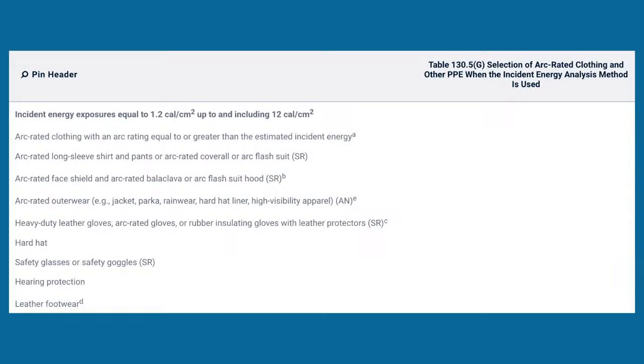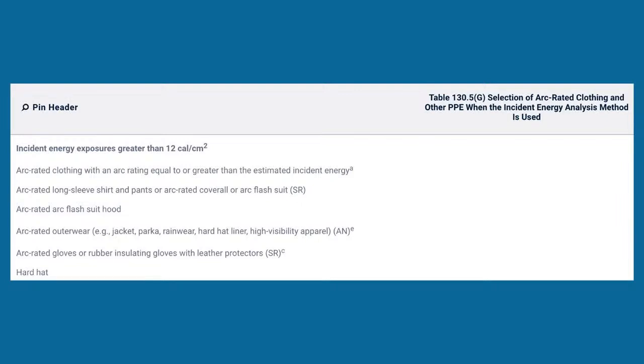Gotcha. To protect yourself. Now, you'll see some things in there, SR. That means selections required between those. Then you have AN. That's as needed. Okay? Now, check this out. Once you get over 12, well, let's just look at one thing here, for example. I'll go down to the third selected item. It says up to 12 cal, it says arc-rated face shield and arc-rated balaclava, or you need to wear an arc flash suit hood. Okay? One of those will work. All right? Now, watch this. As soon as I get up above 12 cal, look, you don't get that option. They tell you have to wear an arc flash suit hood, period.